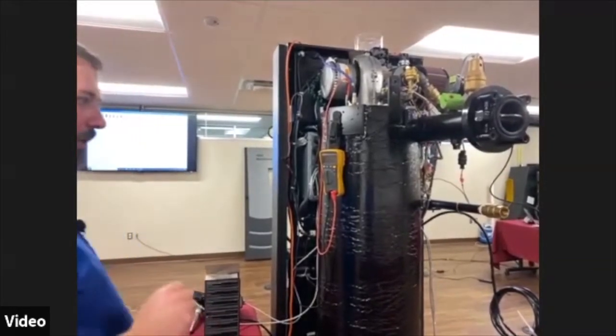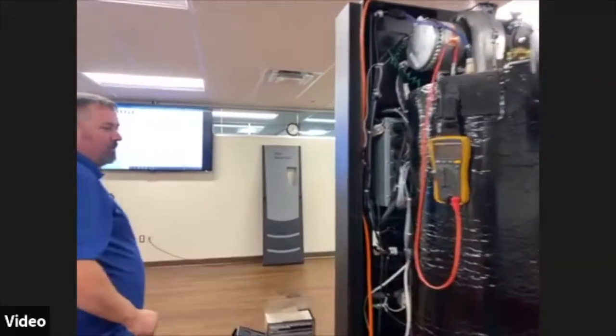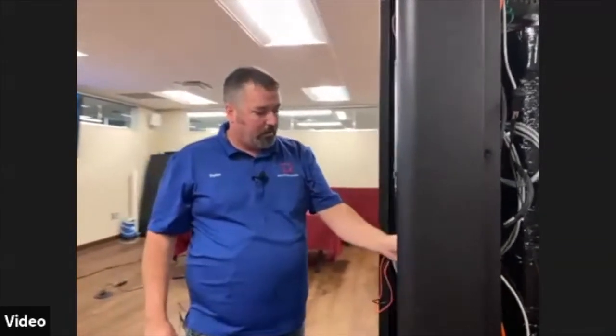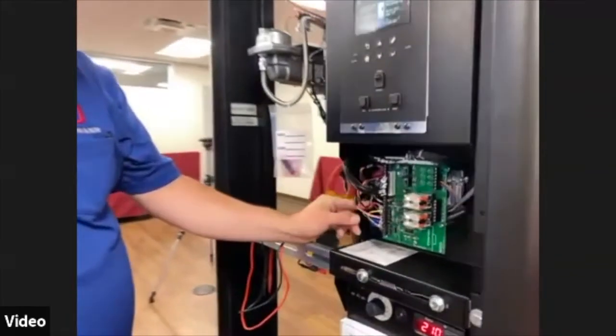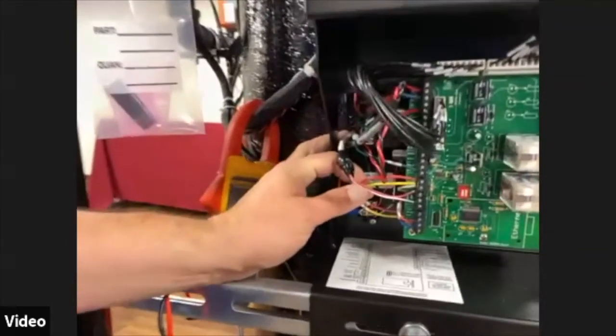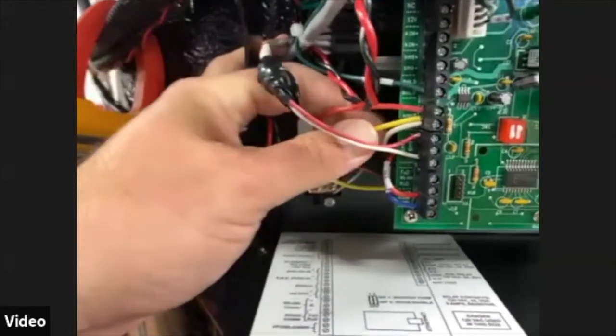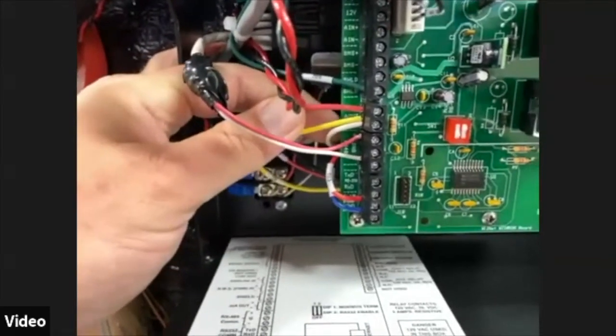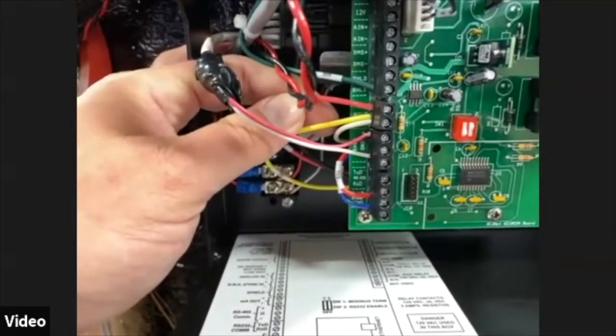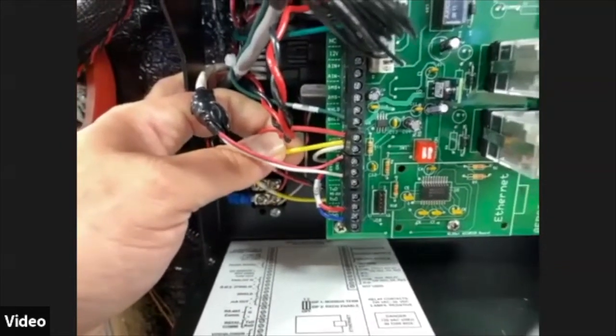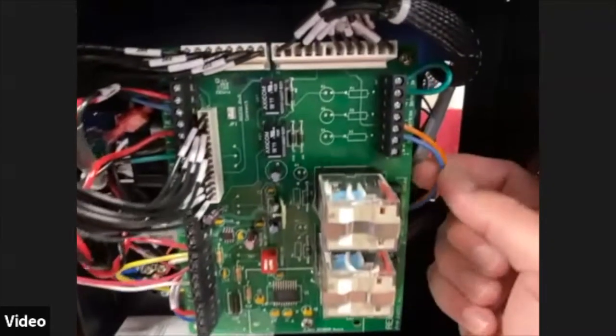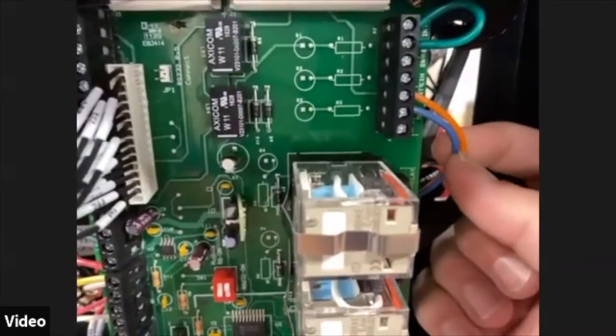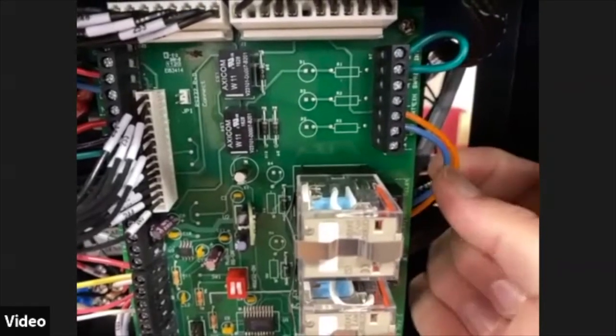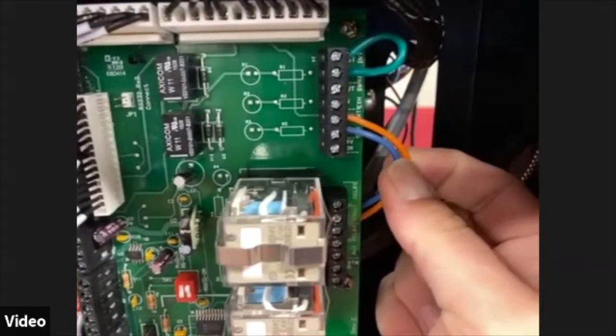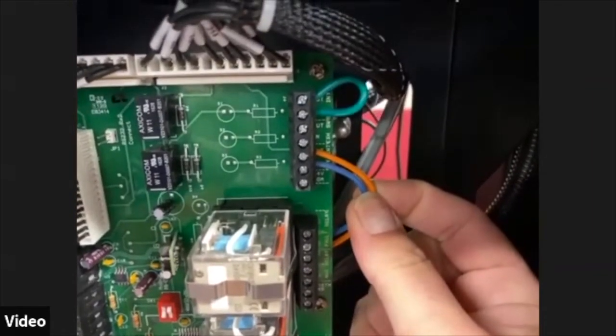From there, I just wanted to real quick show where that isolation valve wires in. The isolation valve is a 0 to 10 volt valve. The power wire is right here with a white, yellow, and red R. That's 10 volts closes the isolation valve. 0 volts causes it to open. And then the end switch is tied into our delayed interlock. That's why I said you set that 120-second timer to give it 2 minutes to fully open or fully close as it needs, and it'll prove where it needs to be.